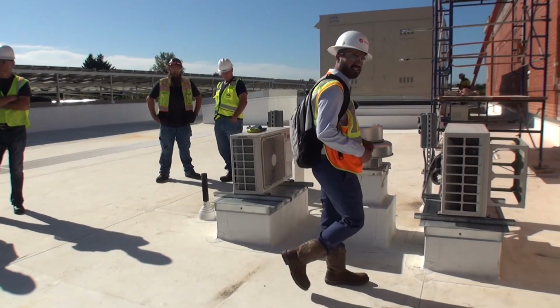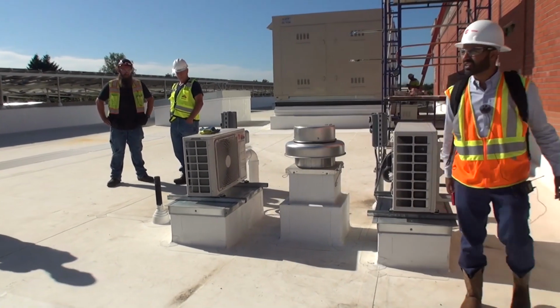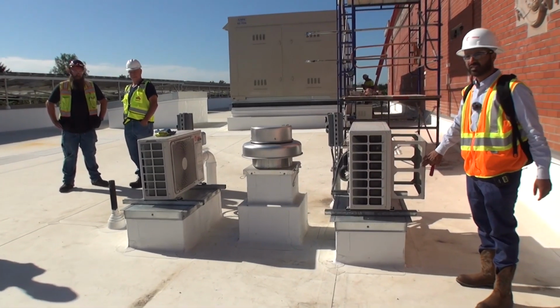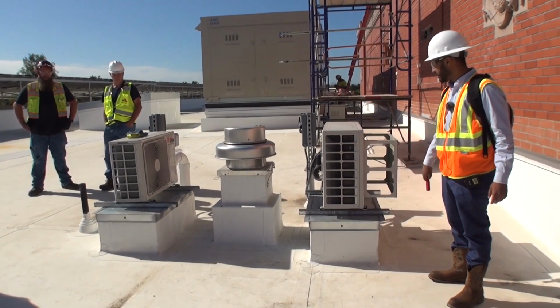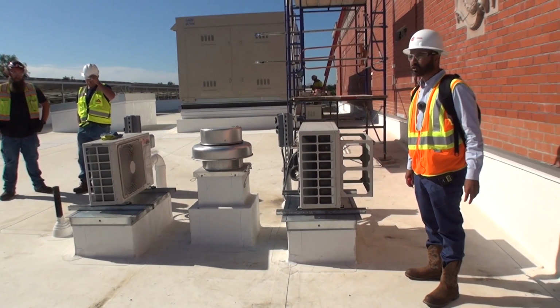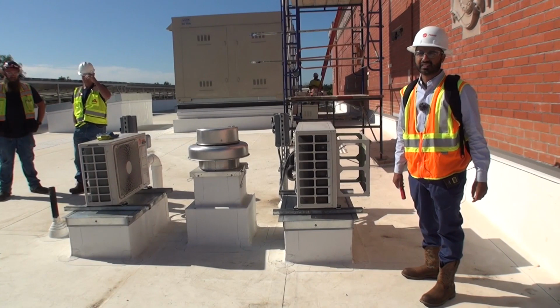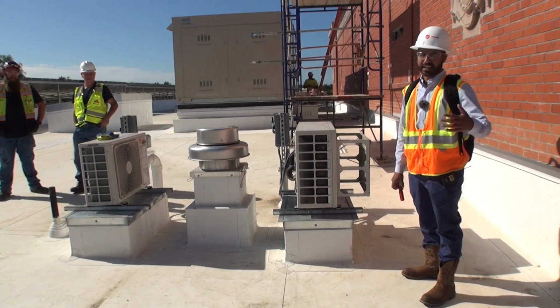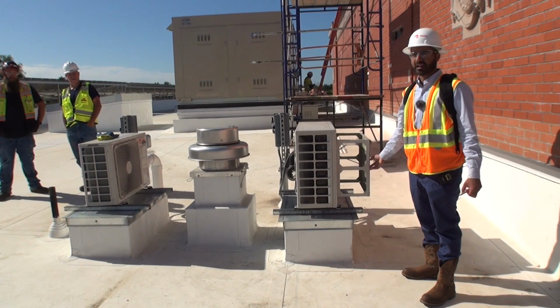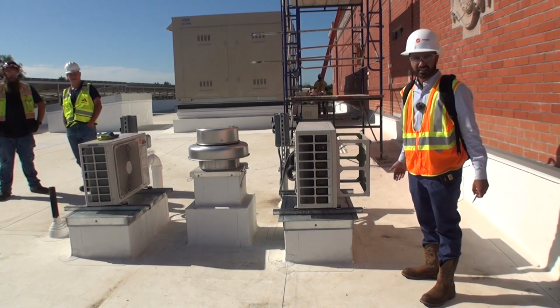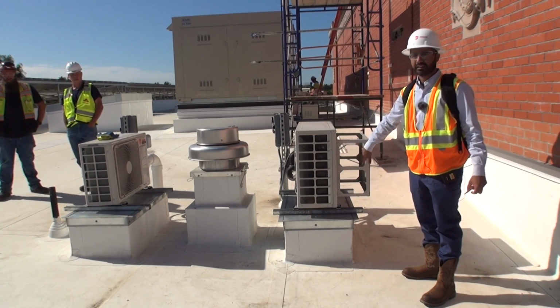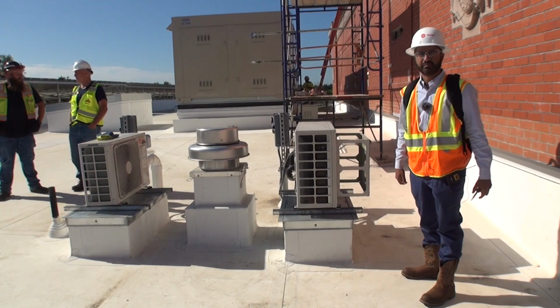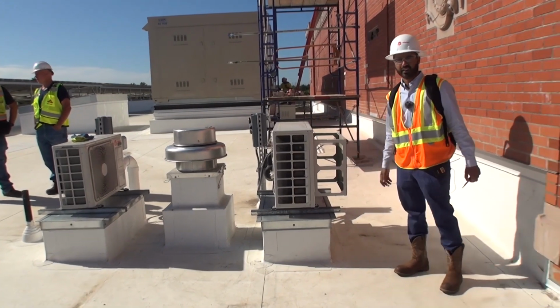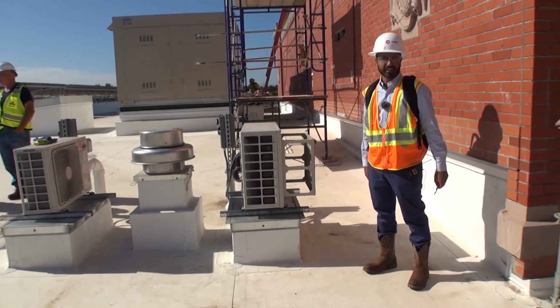Some of the units here are installed with a specific blockage called a wind baffle. What this allows you to do is cool the unit down to 0 degrees, and in case it gets that cold, the wind baffle doesn't let cold air fight against the fan. The fan has the ability to modulate its own speed, so that's what the wind baffles are for, they're here by design.